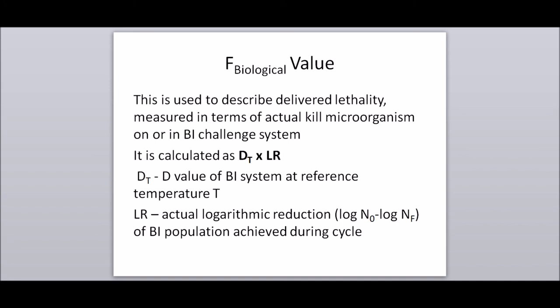F biological is calculated as Dt multiplied by Lr, where Dt is the D value of the BI system at reference temperature T, and Lr is the actual logarithmic reduction — that is, log N0 minus log Nf — of the BI population achieved during the cycle.